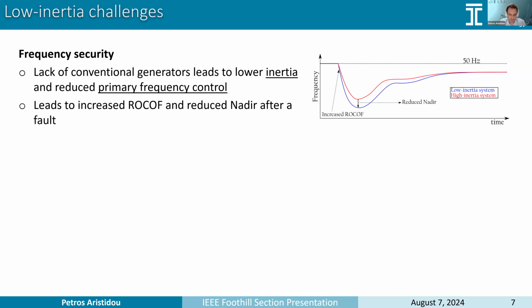The first one, and the one that most people think of when they talk about low inertia systems, is frequency security. The lack of conventional generators, meaning synchronous generators, leads to lower inertia in the system and also a reduced primary frequency control. This leads to an increased rate of change of frequency when we have an event in the system. We see here, for example, a low inertia system and a high inertia system with the same loss of in-feed power. The low inertia system leads to an increased rate of change of frequency and a reduced nadir, a lower dip in the frequency before the system stabilizes. I'm not going to go into more detail on this aspect because the second section is dedicated to it.